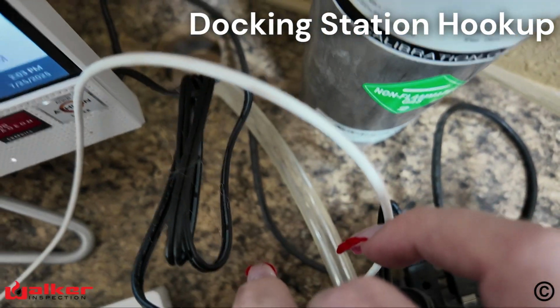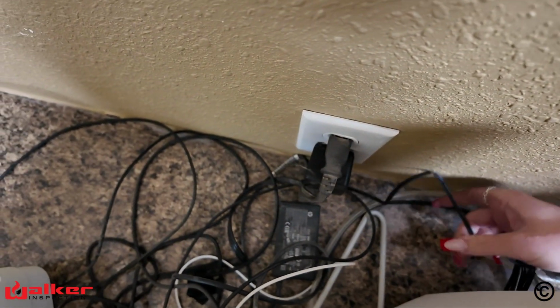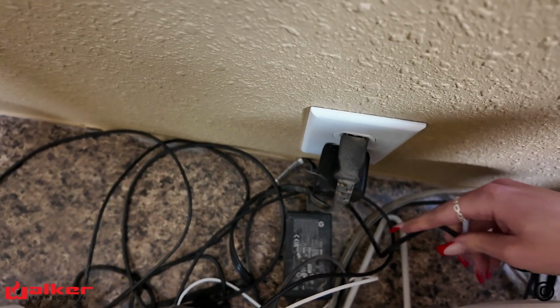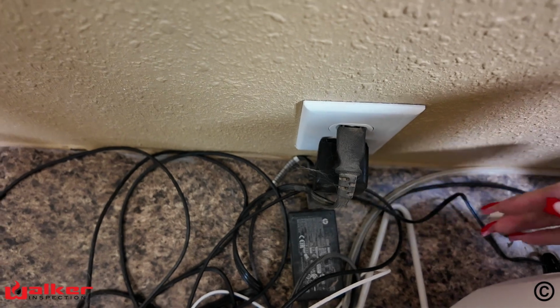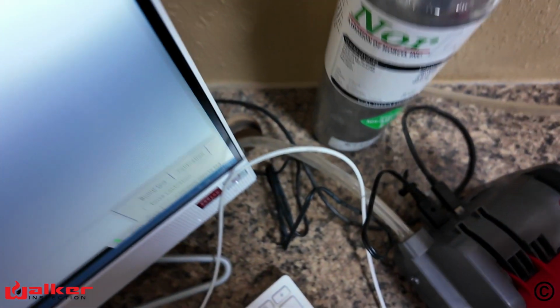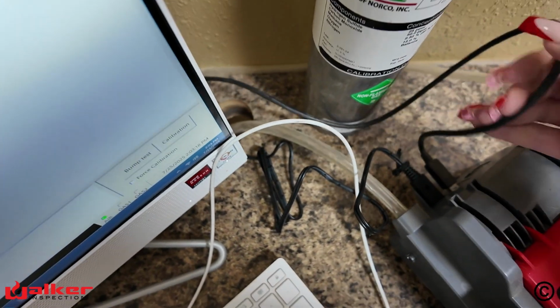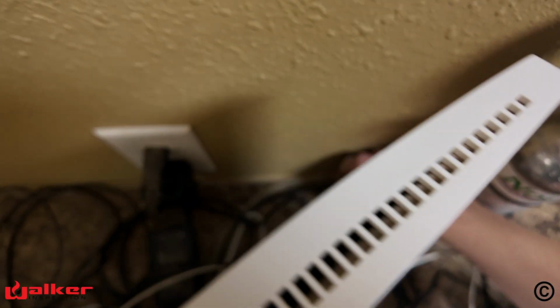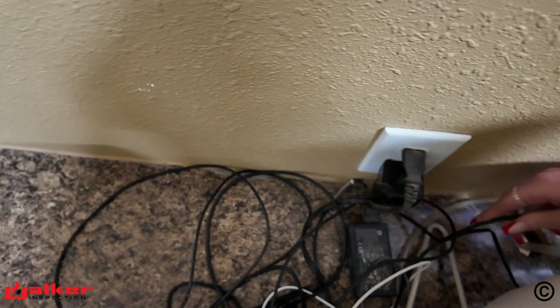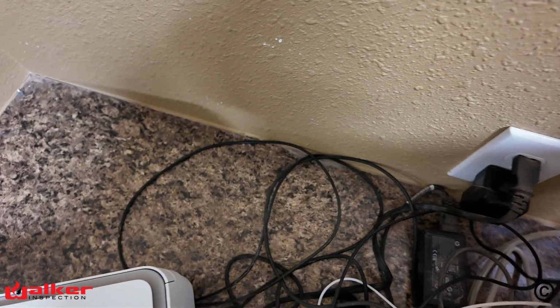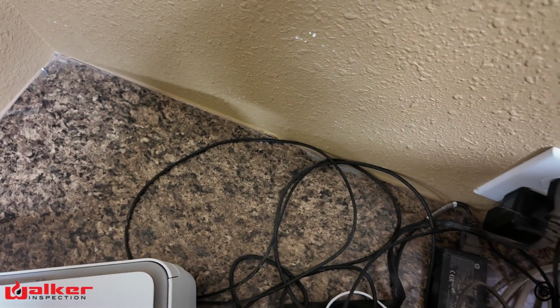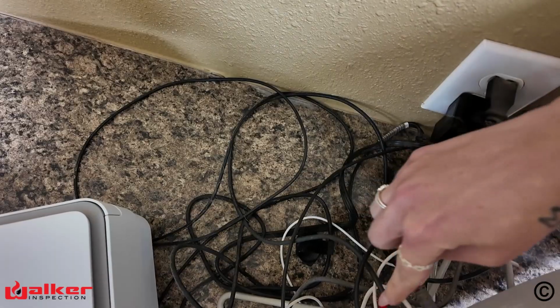Before any monitors can be calibrated or bump tested, ensure that the docking station unit is assembled and hooked up correctly. First thing you will need to check is that the power cord is plugged into the back of the station and into the outlet on the wall. Next, ensure that the docking station cord on the back of the station is plugged in and that it is connected to the computer itself.